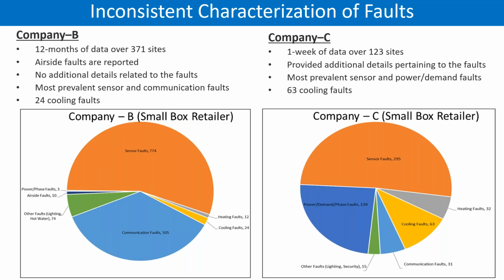What we found is that sensor faults reported by Company B and C were out-of-range sensors. So if a set point were, for example, 72 degrees, and the sensor measured an out-of-range value, say 74 degrees, the companies were binning this as a sensor fault. Other companies might interpret that as a cooling fault or a heating fault, where the system is not able to reach set point. However, Company B and C interpreted that as a sensor fault, and that's where we get this very large 50% slice of the pie.